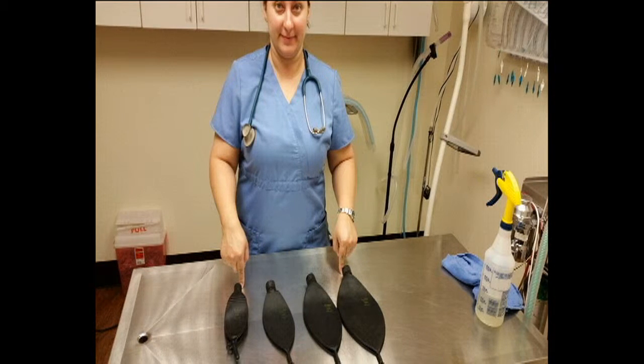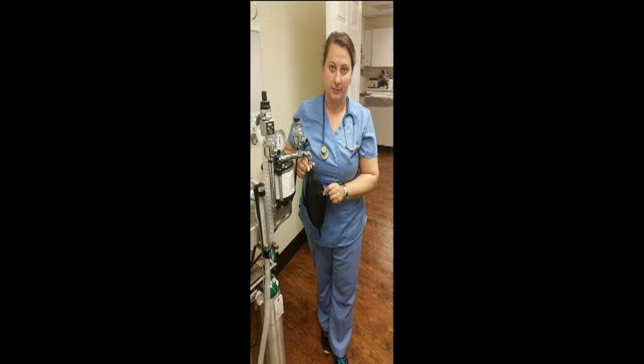Reservoir bag serves as a flexible and expandable air storage reservoir. Reservoir bags come in a variety of sizes, from half a liter to 30 liters. The size of the bag depends on the size of the patient. The reservoir bag allows us to deliver fresh oxygen and anesthetic gases by simply squeezing the bag. It allows us to assess respiratory rate and tidal volume. It also minimizes atelectasis by ventilating the patient every 5 to 10 minutes.